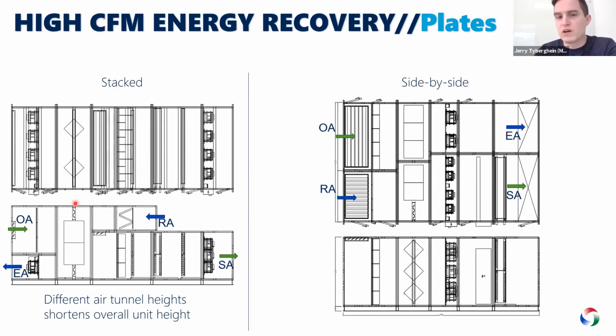This is a partial outside air unit, so you have an economizer. Your outside air comes in here, hits this plate heat exchanger bank, and crosses down into the supply airstream. Return air comes in here, and it exhausts through the core and out through these ECM fans. There's also a recirc damper because it's partial outside air. If you take one thing away from this, it really helps you save on height, because if you need 500 feet per minute for your cooling coil on the bottom, say this is an 80-inch tall section, on the top you only have filters. So if we can angle those, you can shrink this height down to about 40 inches.